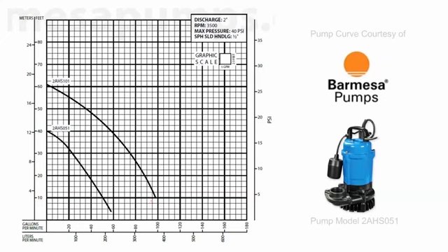Another thing to take note of when reading a pump curve is that oftentimes it's a good idea to pay attention to the scale of the graph that you're reading, and most often each pump curve is going to have a slightly different scale. The scale on this pump curve is 2.5 feet per vertical square, but 5 gallons per minute per square horizontally.